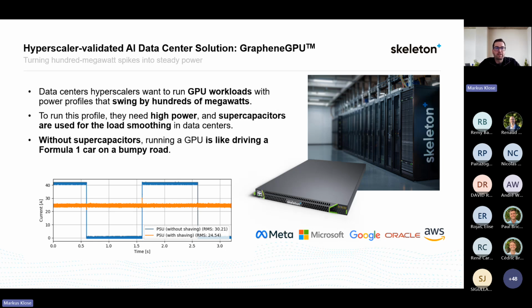The orange line is the same load profile on the GPU, run in conjunction with our module, and you can see the power draw is much more stable than before, because the supercapacitors take up the energy when it's released and give it back to the system when needed. This can be done constantly, 24/7, with these 1 second on or off cycles.